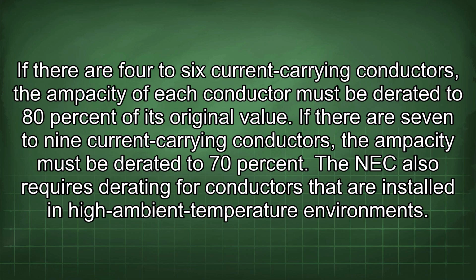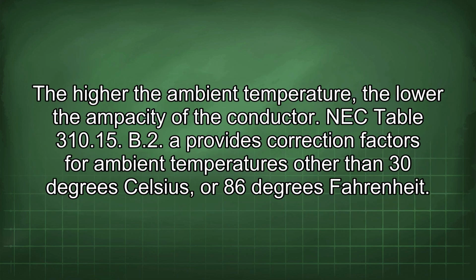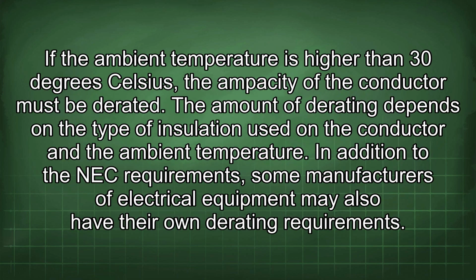The NEC also requires derating for conductors that are installed in high ambient temperature environments. The higher the ambient temperature, the lower the ampacity of the conductor. NEC Table 310.15(B)(2)(a) provides correction factors for ambient temperatures other than 30 degrees Celsius or 86 degrees Fahrenheit. If the ambient temperature is higher than 30 degrees Celsius, the ampacity of the conductor must be derated. The amount of derating depends on the type of insulation used on the conductor and the ambient temperature.